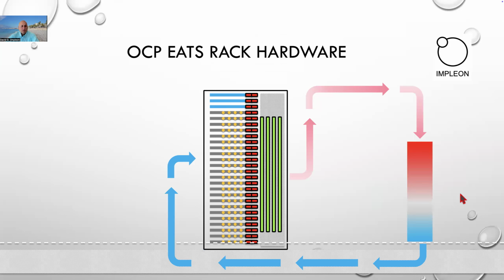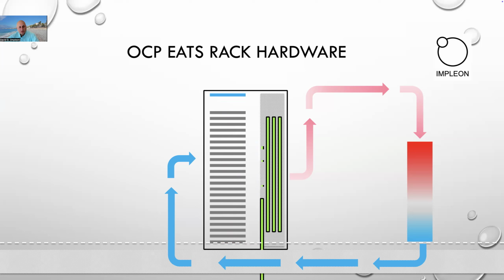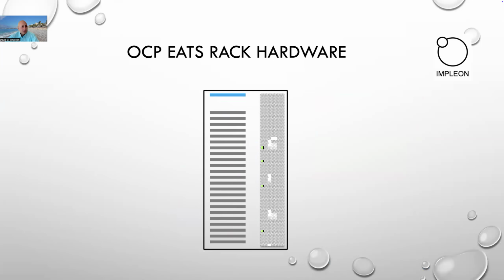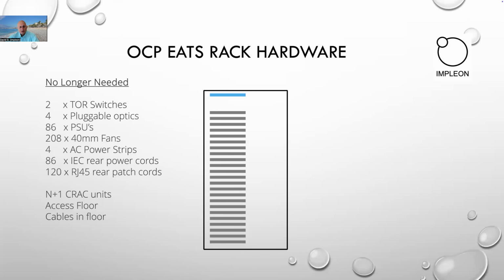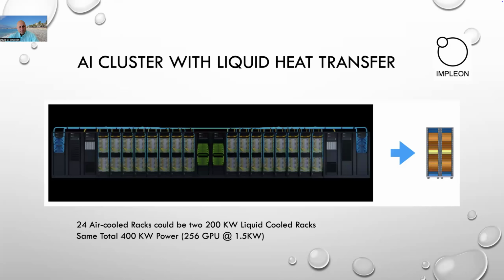Another thing is servers and rack level decarbonization. By shifting from OEM to OCP servers, we can take away 4 fans on each server. We can take away the power supply units because we have a rack level power supply shelf. We take away another two top of rack switches. We take away the power distribution unit because we have a centralized busbar. And we take away CRAC units because we create new conditions for the servers. And we take away all unnecessary strips, cords, etc.